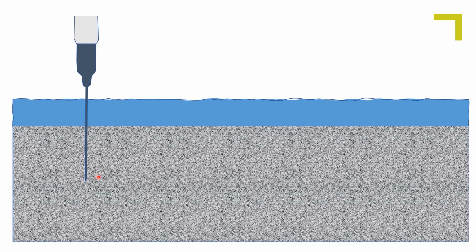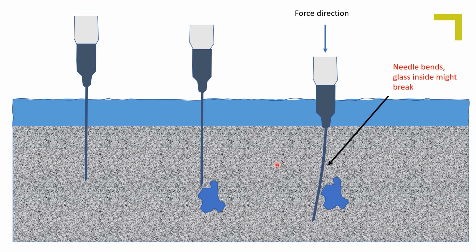The needle protection does not make it impossible to break. If the needle is pushed into a matrix containing obstacles which are not easily moved, the needle will start to bend, and as the sensor is pushed downwards, the glass inside the needle might break. A 500 micrometer tipped naked glass sensor with a conical design is actually often less prone for breakages when profiling in matrices.